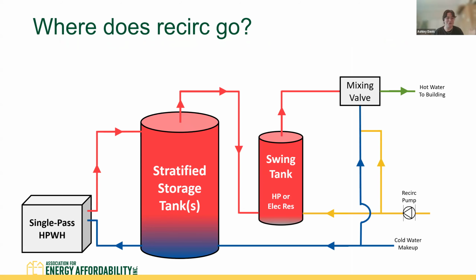So again, you got to think about where your recirc water is going to go. You know, your warm incoming water. It's not what your single pass heat pump water heater likes. You'll see some sort of swing heater installed as well, sending recirc water to the swing heater and to the mixing valve. Next slide.